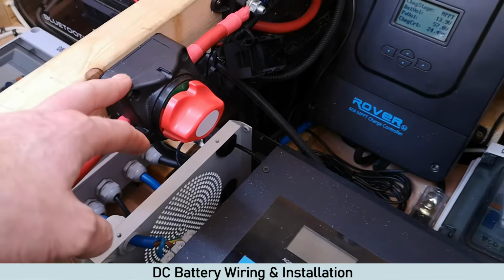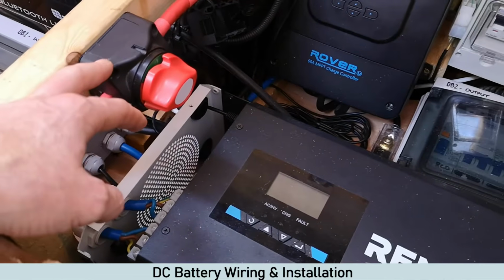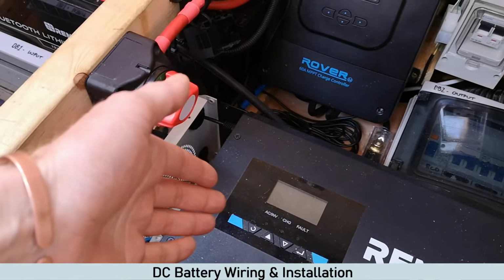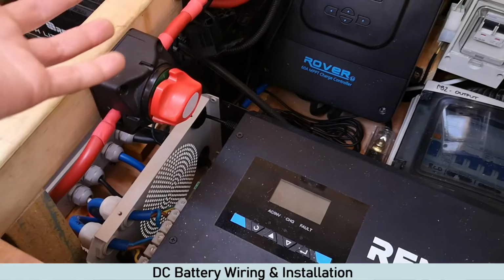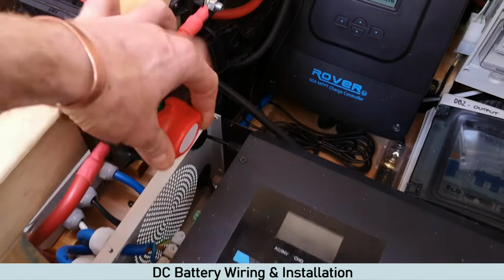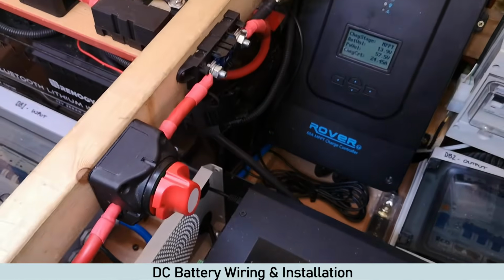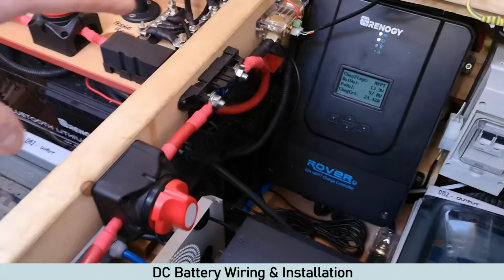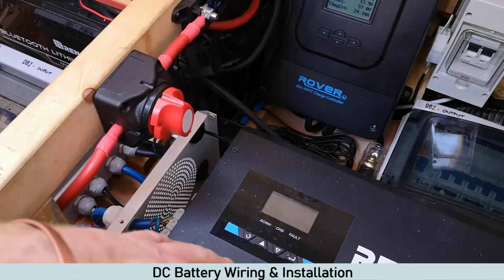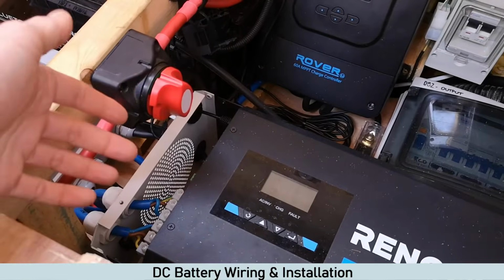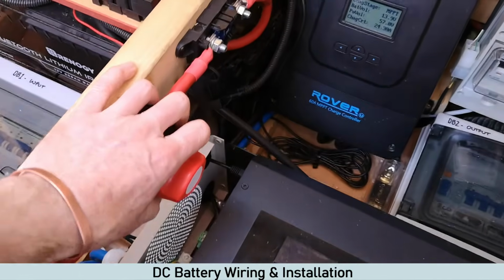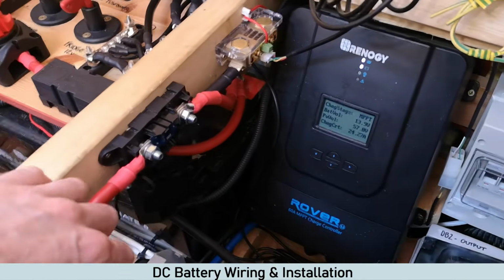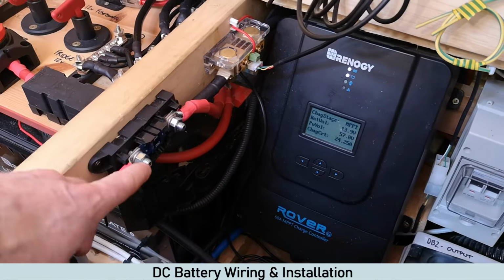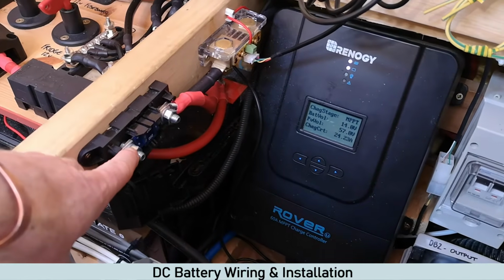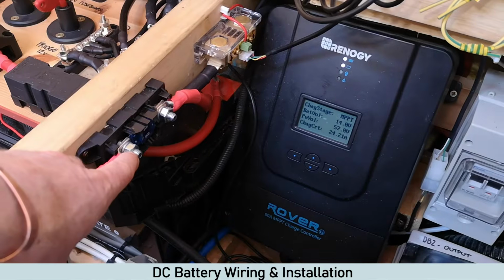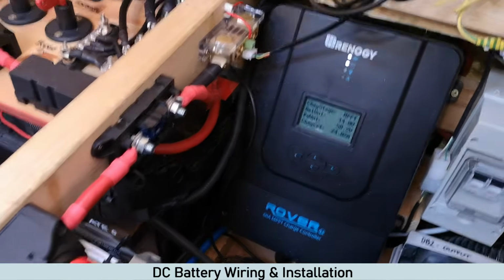The reason why we've got it is if we ever need to do any maintenance or we need to switch off the inverter charger if there's a fault or anything like that, we can turn it off there, literally just do that. And then it isolates it from the rest of the installation, so it's not going to cause any issues, or we can remove it or do work on it, anything like that. Obviously, if you don't have this to isolate it, you've either got to disconnect the battery terminal, or you've got to take the fuse out, which obviously is held on by nuts. So you've got to get a tool out to isolate it.